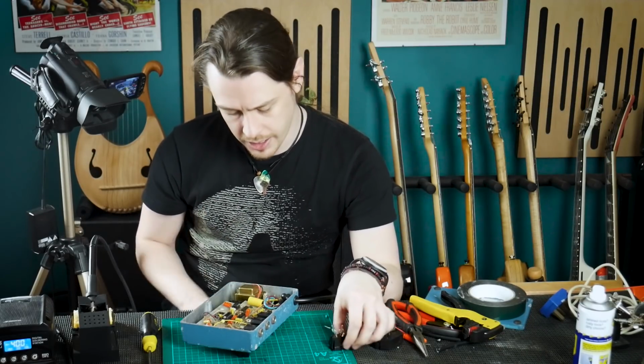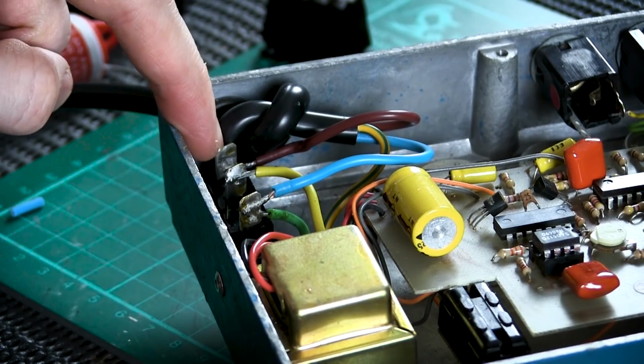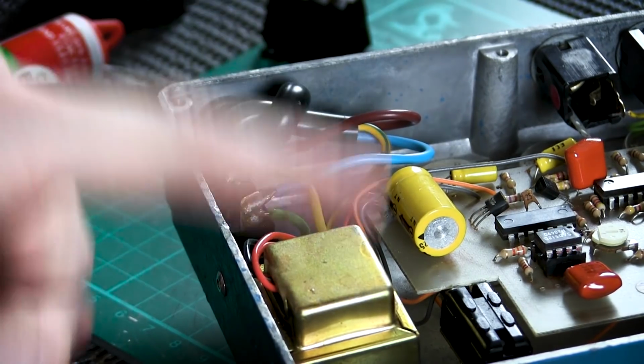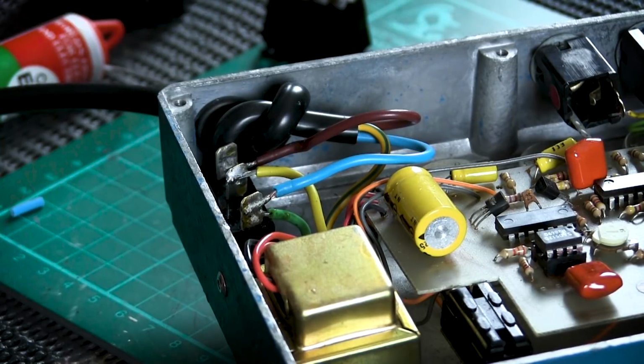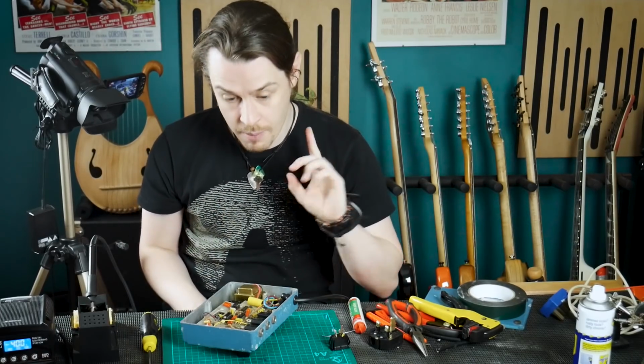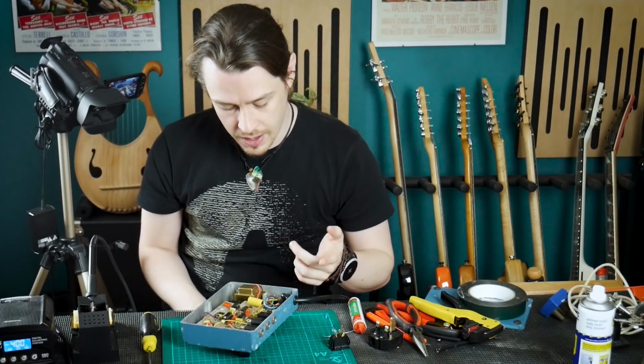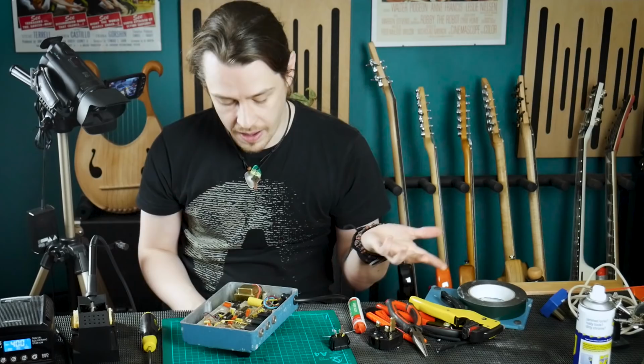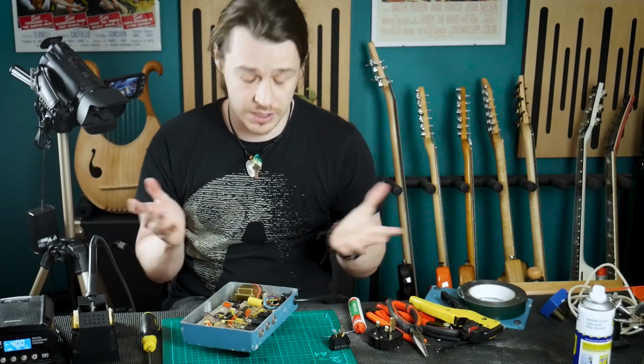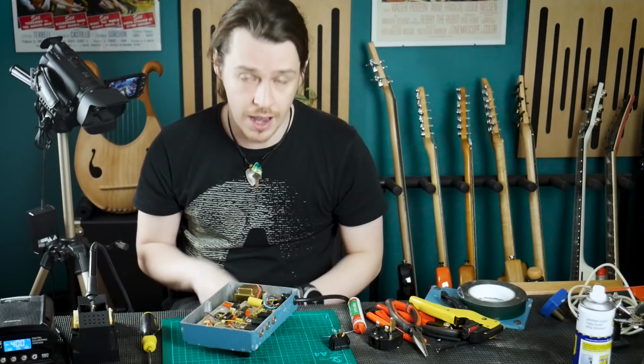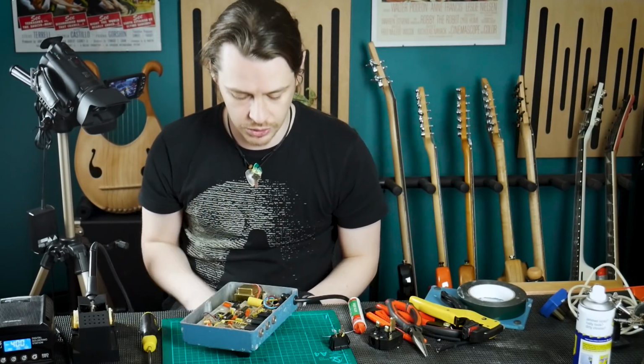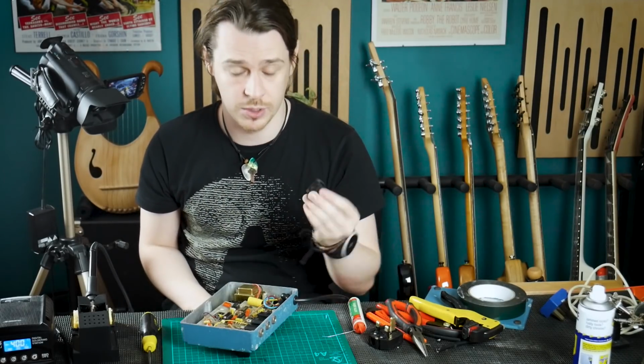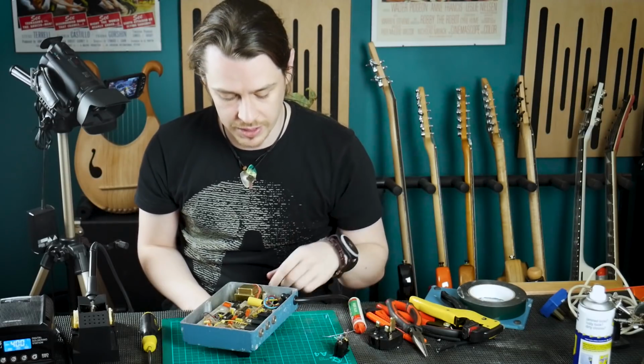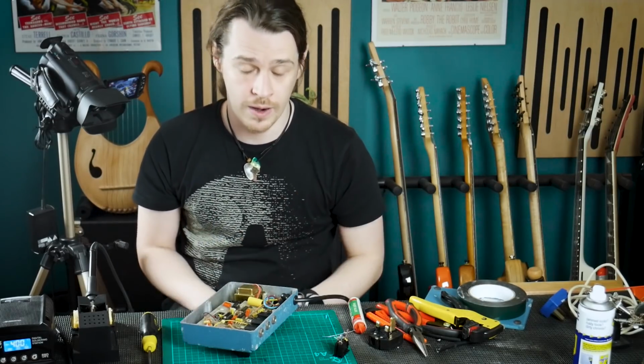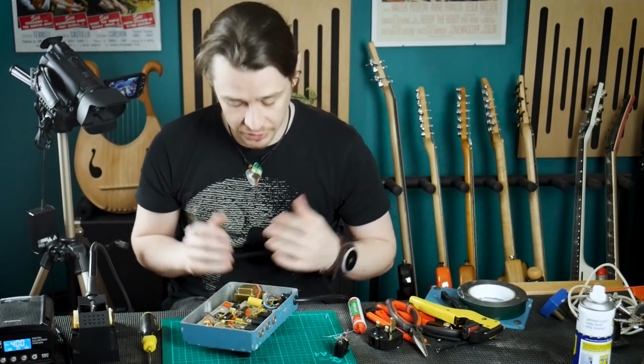So the way I've wired it now, the live comes in here, and in the on state it still goes through the yellow wire, through the transformer, green wire, back to neutral - exactly the same as before. But now, in the off position, the live goes to absolutely nowhere, which seems much more reasonable, and we don't have this power loop cycling through the switch, which is possibly why the switch burnt out in the first place. So now the live just goes to an open circuit, and nothing can happen.